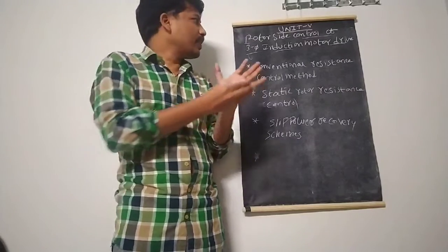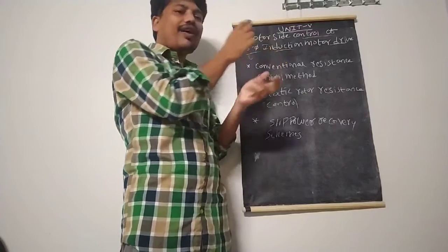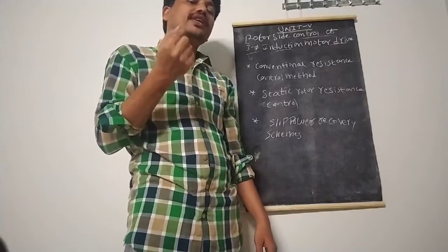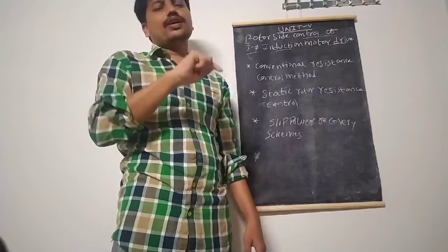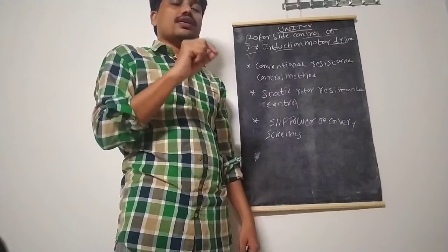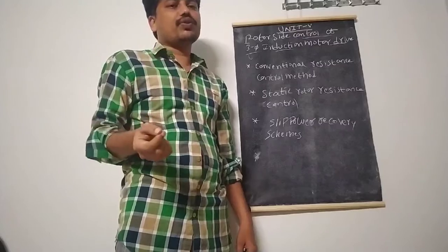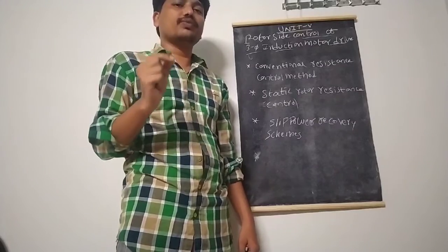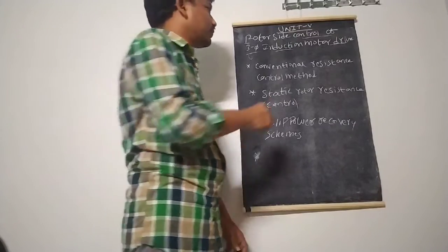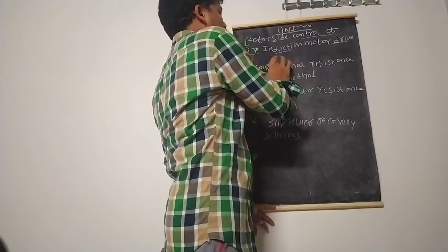The rotor side control method is only applicable for the slip ring induction motor, not for the squirrel cage induction motor. The stator side control method can be applied to both squirrel cage and slip ring induction motors. The other name for the slip ring induction motor is the wound rotor induction motor.